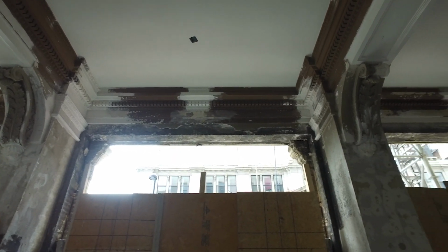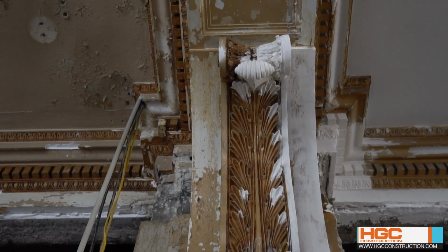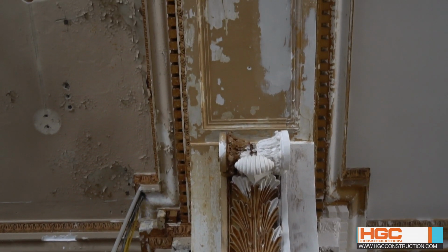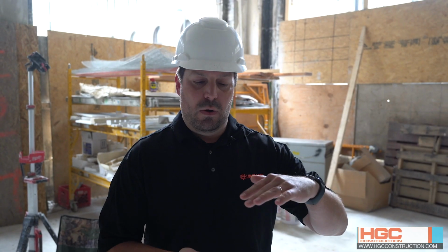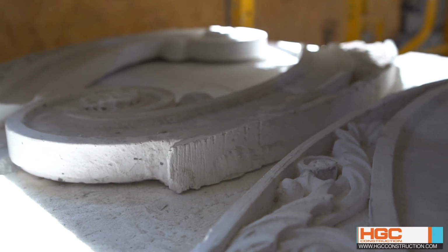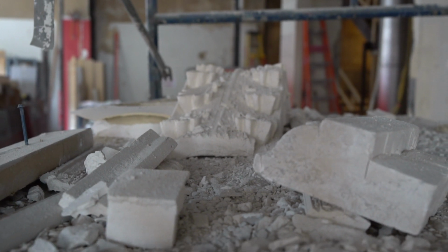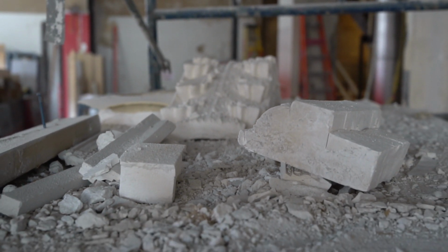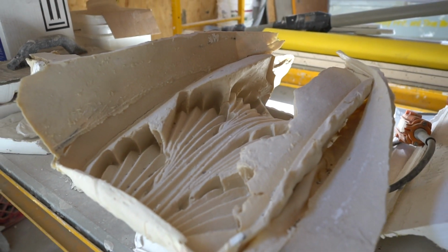So you can see the space is grand, with original ornate ceilings that we're bringing back, preserving and restoring. Similar to the basement level and the first floor, we have this sandwich condition where we don't want to penetrate through any of the decorative or ornate plaster or historic elements. What we did is we threaded up above, created a false slab to route our plumbing pipes, and also selectively put bulkheads and soffit ceiling conditions to route ductwork. That way we can keep this space open to the original design intent and not impede on any of the ornate plasterwork.